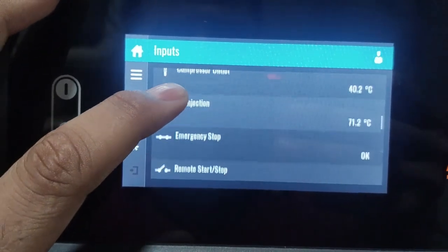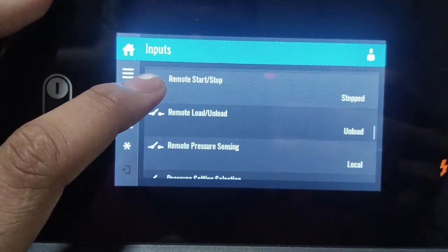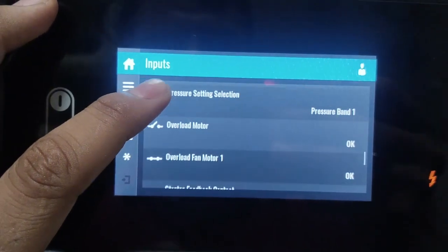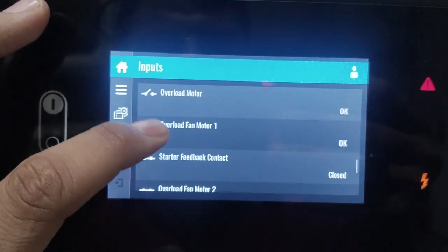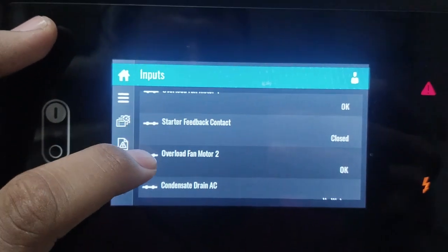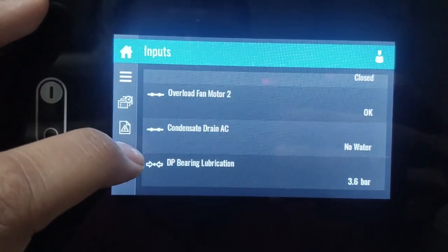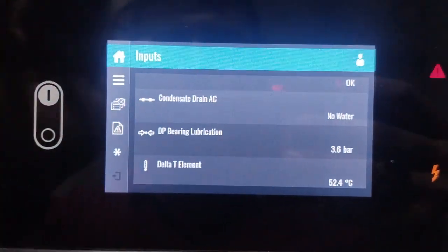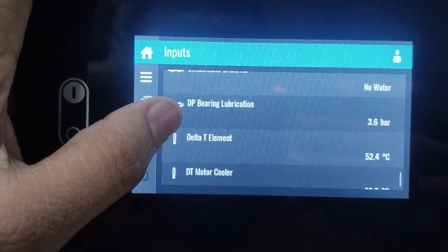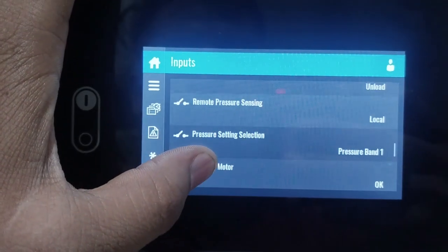Compressor outlet was 40.2 degrees, oil injection 71.2 degrees, and other parameters are normal. You can see all parameters like overload fan motor okay, starting feedback contact okay, overload fan motor okay, condensate drain AC no water, DP bearing lubrication 3.6 bar, delta T element 52.4 degrees, and DT motor cooler 28.9 bar.